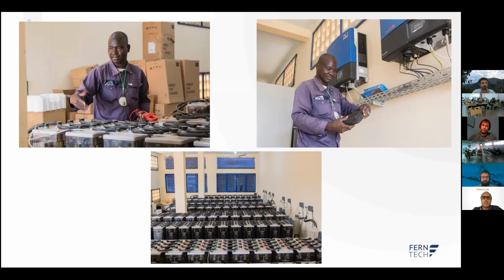Yeah, absolutely. And not only during installation, but also during maintenance. FernTech in this case is going to help a lot with maintenance, but at the end there should be someone there doing the maintenance, cleaning the batteries, topping up with distilled water, cleaning the terminals for corrosion, checking specific gravities and temperatures. So this adds cost and complexity to the project itself. Yeah, it's a good pilot project, but in terms of battery, I would probably use other options.